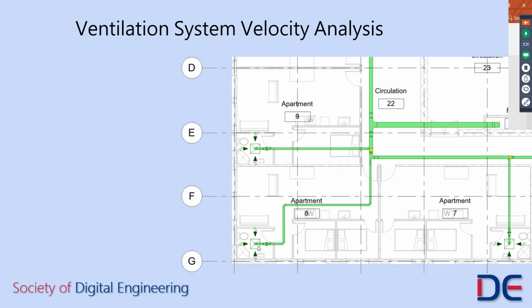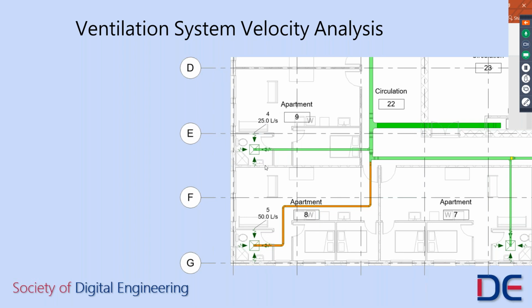Now, what if we take this diffuser in the bottom left-hand corner and increase it from 25 liters per second to 50 liters per second? It has automatically recolored this piece of duct to show that the velocity is higher than we wanted. And this is a very simple guide for any engineer to see that as we change the values associated with our extract grills, this is having a material effect on the ventilation system. And the bright orange says, hey, wait a minute, I think we might need to do something here. Either the flow rate is incorrect or the velocity is too high.